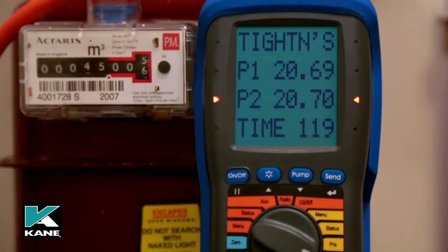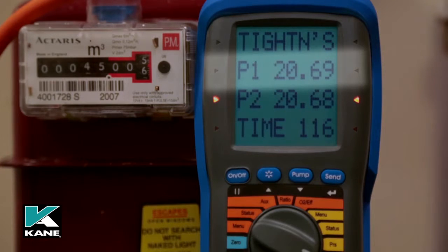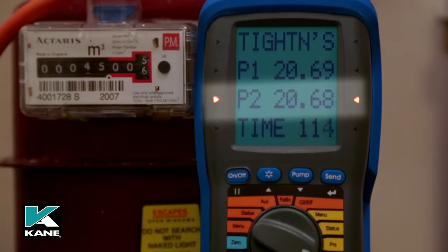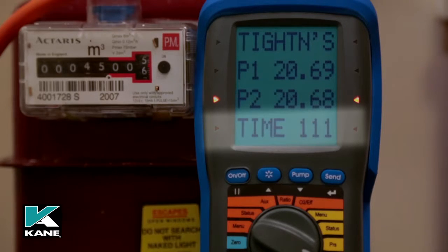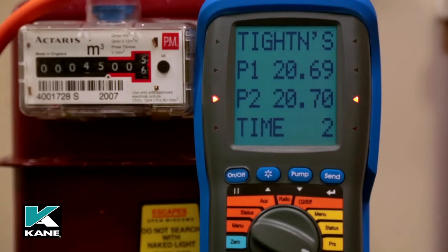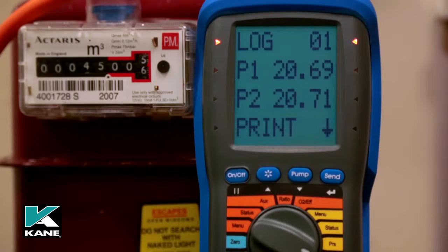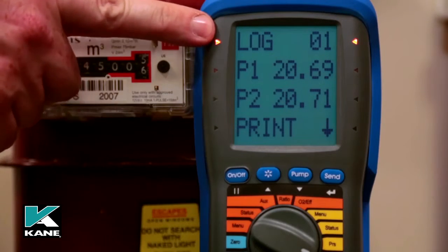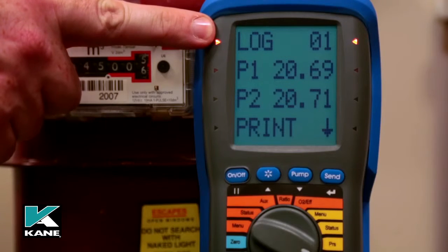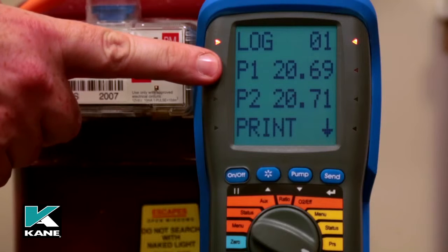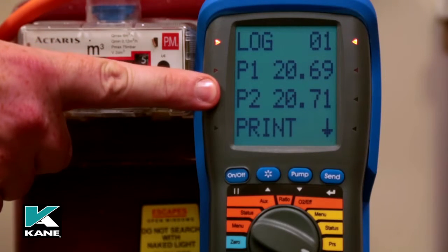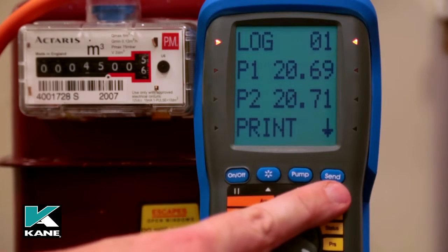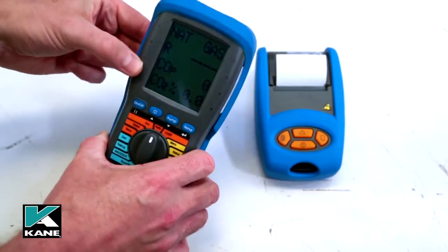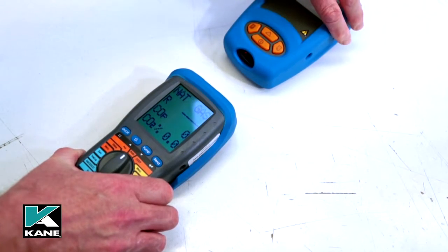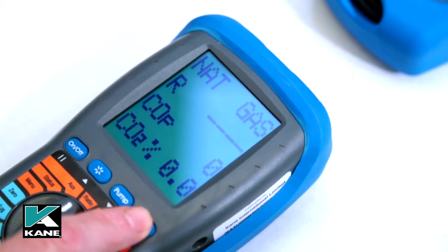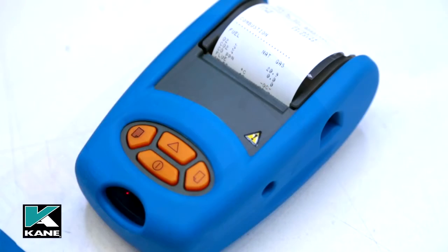The display is as follows: pressure at start of tightness test, real-time pressure reading, tightness default time is 2 minutes. This can be changed via menu. When complete, the display will show let-by and tightness test are automatically stored as a log number, pressure at start of tightness test, pressure at end of tightness test. The test can be printed immediately or later from the memory. To print the reading, align the printer to the analyzer, make sure the printer is switched on, and a short press of the send key will transmit the readings to the printer.